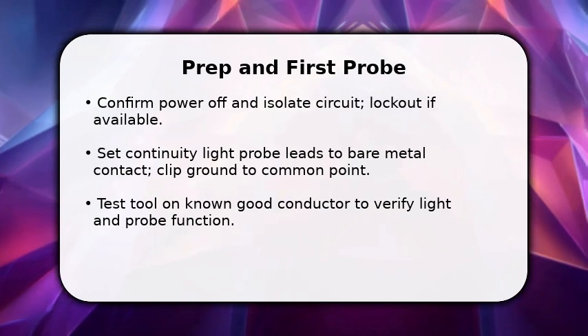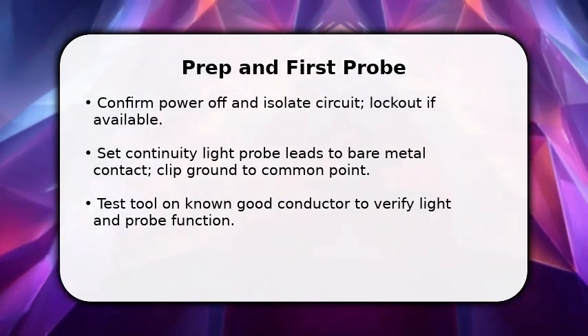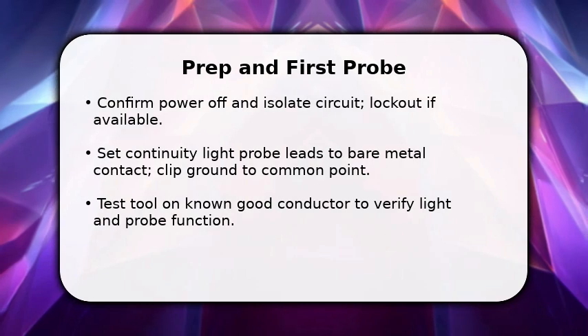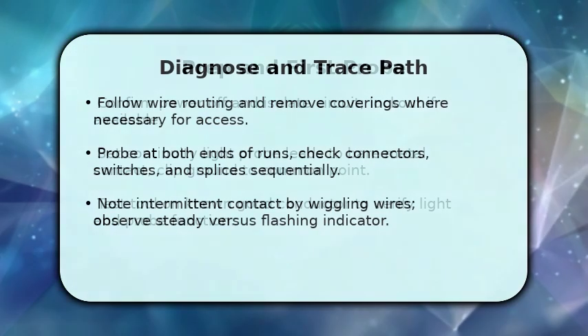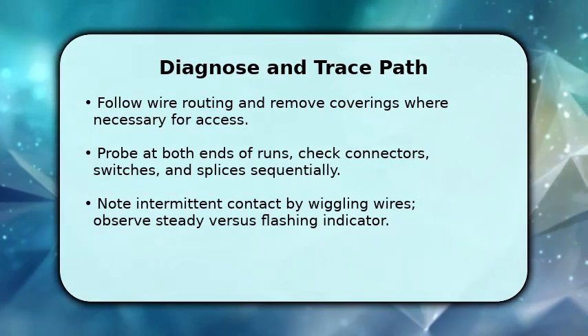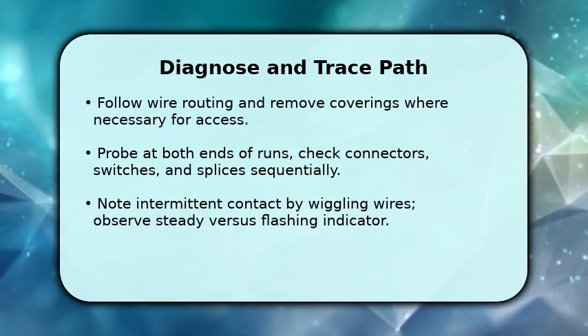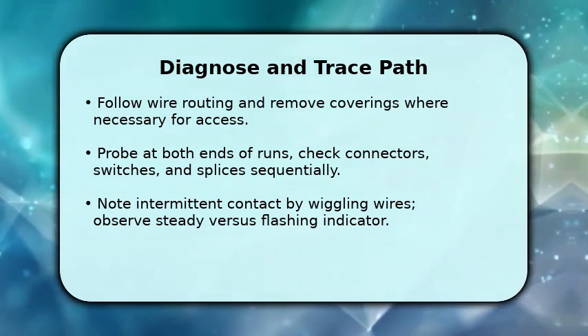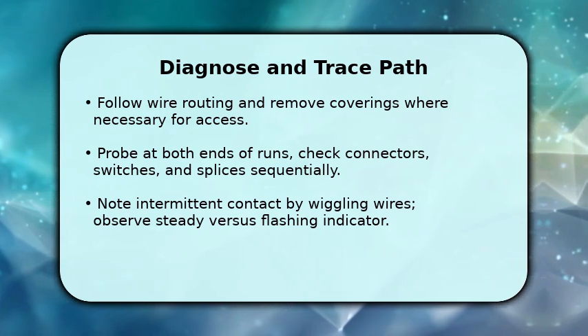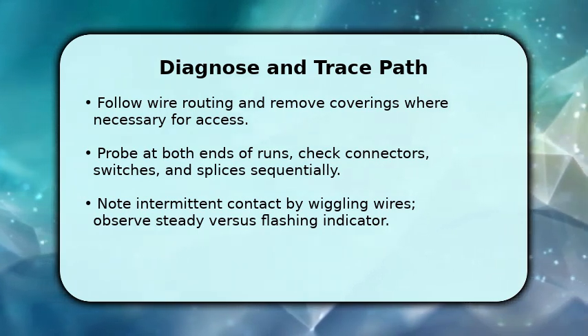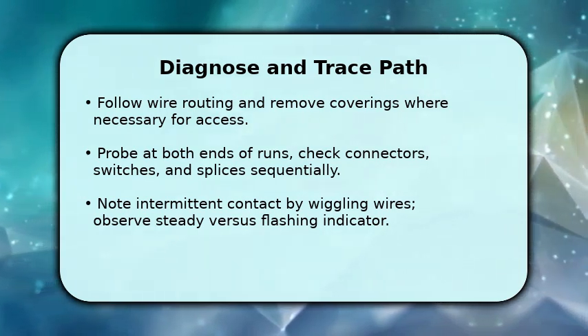With the tester verified, trace the wiring path methodically, expose junctions, or remove terminal screws so the probe contacts metal. Test at each end of a run and at any intermediate splice, pressing the probe tip firmly against the conductor. As you progress, wiggle joints and move connectors to reveal intermittent faults.